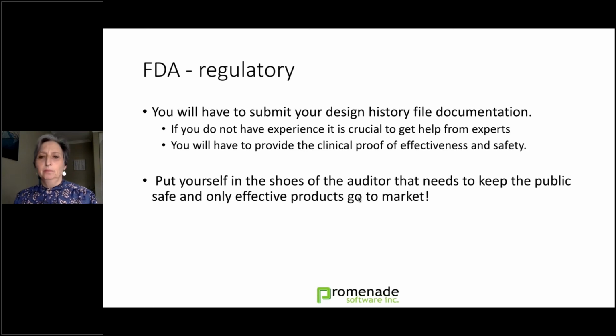Often a lot of those are not difficult. I think I've covered the big pieces, the requirements, the design, the risk analysis, and the verification. But there's a lot of small pieces that need to happen as well. If you're using off-the-shelf software, can that cause a problem? That should go into your risk analysis. But a person that's more aware of these type of things that they'll be looking for at the FDA can help you beef up your submission to cover that.